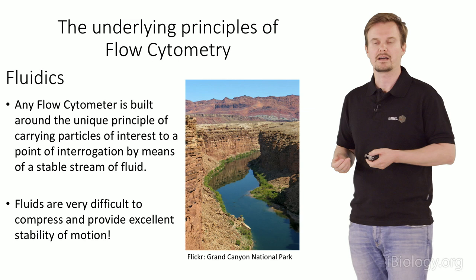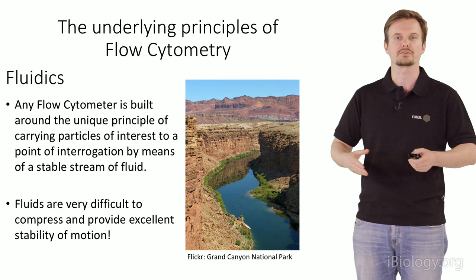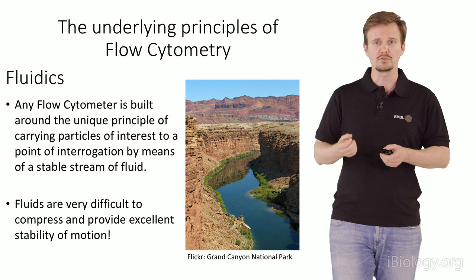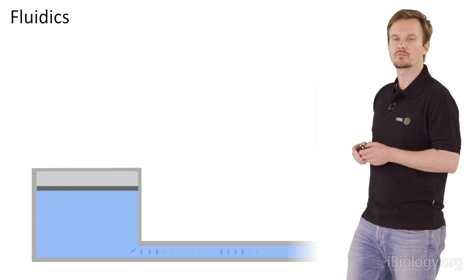The first thing we have to think about is fluidics. In the flow cytometer, we have a system that runs like a river. In perfect conditions, this river always flows at a certain motion with a certain volume per time. In the flow cytometer, we have a system which runs with a laminar flow, transporting a certain volume in a certain time, so we always have constant speeds. Fluids are perfect for this because they're very difficult to compress — when we apply a constant pressure, we also have constant flow.